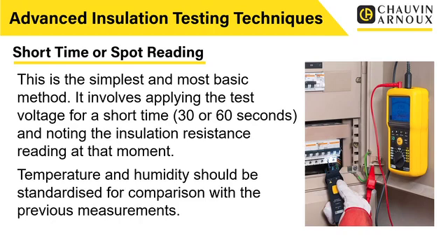So don't be afraid to apply this for, say, 60 seconds before you actually do the test. Does it appear to be stable? If not, then potentially you need to allow more time to get that stable reading. So just be aware that we can carry out spot tests, but we do need to allow time for that reading to stabilize.